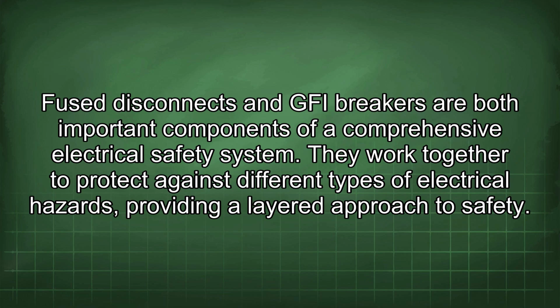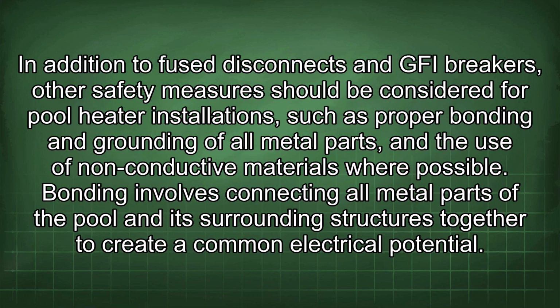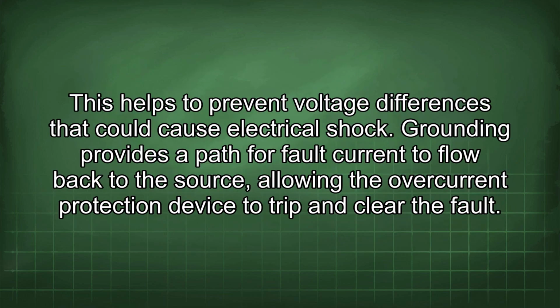They work together to protect against different types of electrical hazards, providing a layered approach to safety. In addition to fuse disconnects and GFI breakers, other safety measures should be considered for pool heater installations, such as proper bonding and grounding of all metal parts, and the use of non-conductive materials where possible. Bonding involves connecting all metal parts of the pool and its surrounding structures together to create a common electrical potential. This helps to prevent voltage differences that could cause electrical shock.